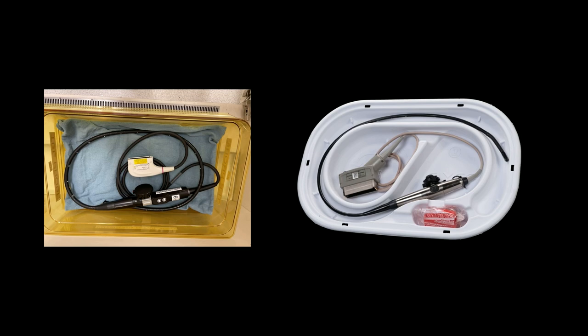When they lay like that, they tend to get twisted, and they stay twisted. After a probe's about 6 months to a year old, you'll notice that the transducer used to be aimed in one direction, and now it's 90 degrees to that, just from laying in a twisted position. The manufacturers recommend that you don't store them like this. Civco makes a special case, the one on the right, if you're just going to carry the probe. It's a little bit better than ours because it doesn't allow the parts to get too curled up.